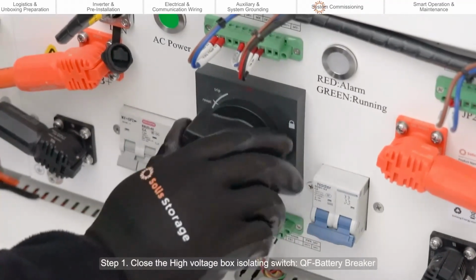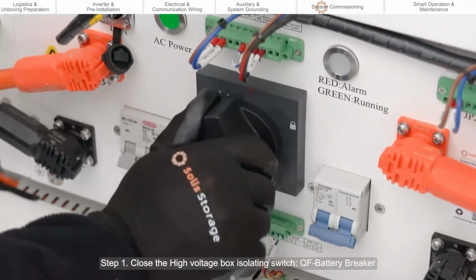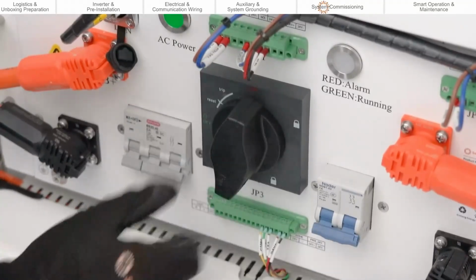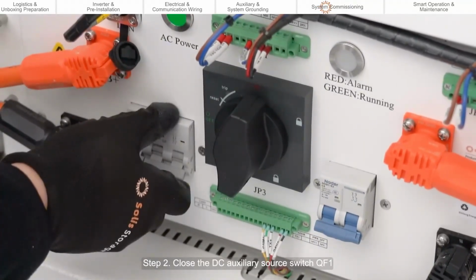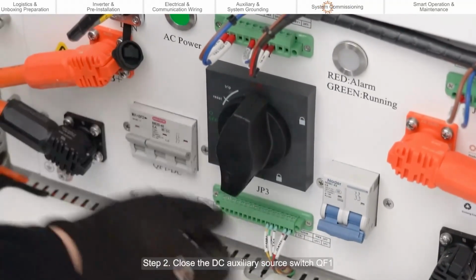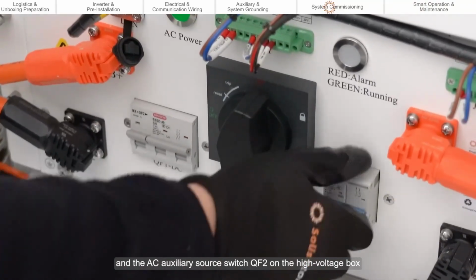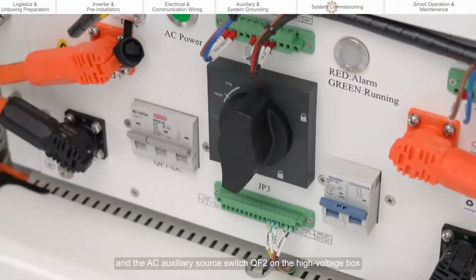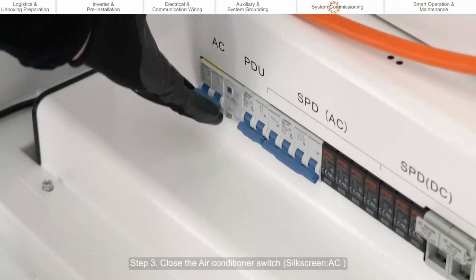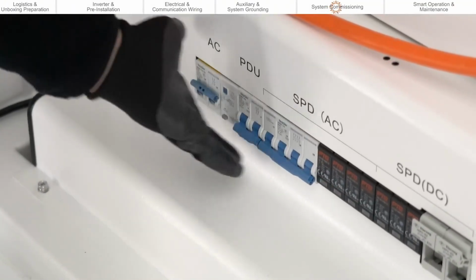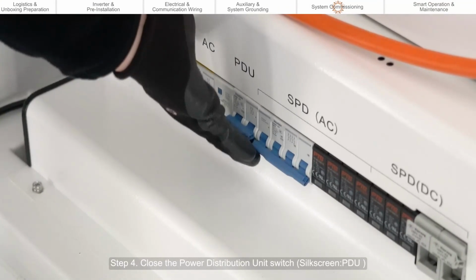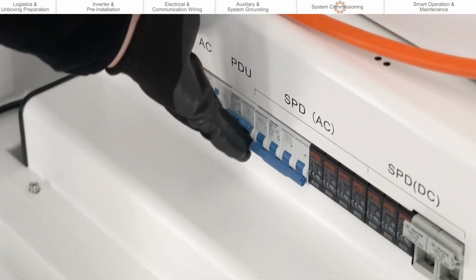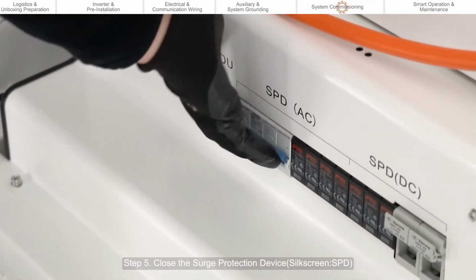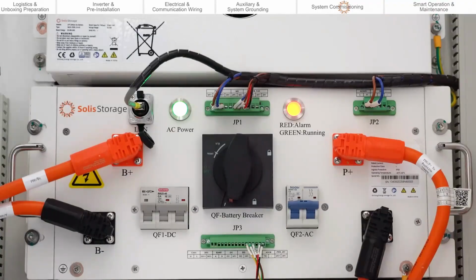Step 1. Close the high voltage box isolating switch, QF battery breaker. Step 2. Close the DC auxiliary source switch QF1 and the AC auxiliary source switch QF2 on the high voltage box. Step 3. Close the air conditioner switch. Step 4. Close the power distribution unit switch. Step 5. Close the surge protection device.